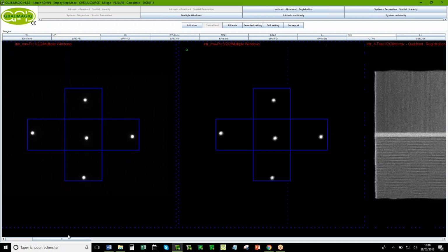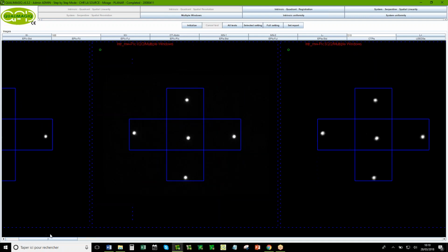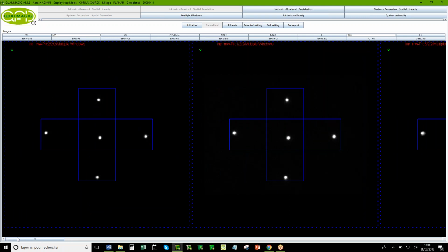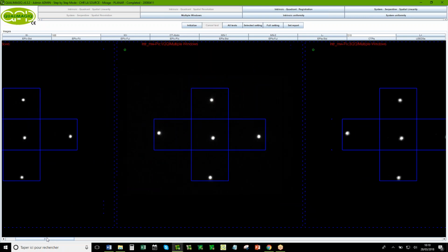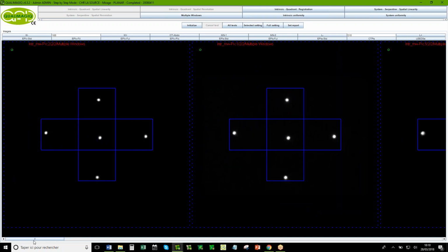In this case, they use a gallium source. It's a very expensive radioactive source, but they have 3 different energies. But you can use also indium with only 2 energies, and it's less expensive. So it's also a possibility. You are not obliged to test 3 different energies.